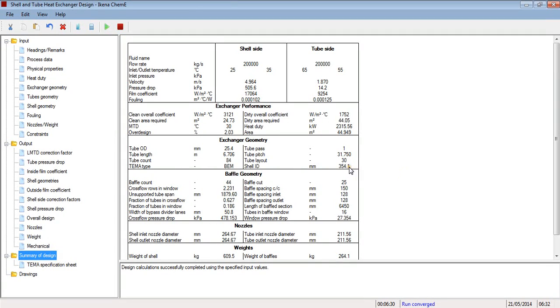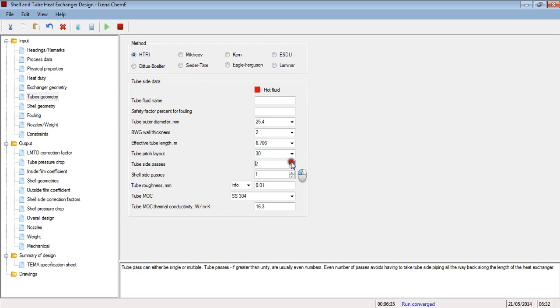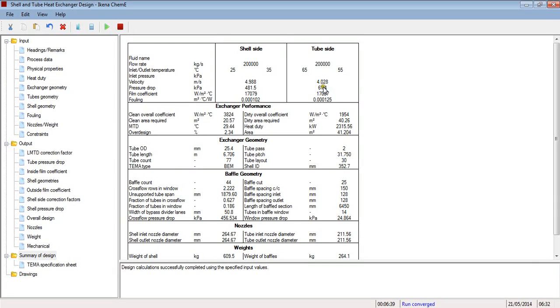Shell ID is 354. Okay, what we can do is increase the number of passes to 2 and look at the pressure drops. Yeah, this looks good. This is slightly higher. This is higher as well, but that's fine for now. We will assume that this is a good pressure drop. This is acceptable to us.